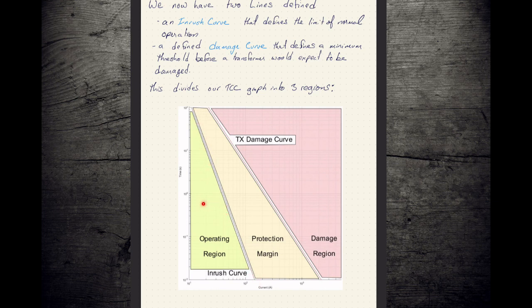And if you plot the points from the inrush curve on a log-log graph, it makes a mostly straight line. And we know that anything on this side, so anything less than our inrush curve, represents our normal operating region, right? Everything's hunky-dory as long as you're not above the inrush line. The inrush line is what we define as the upper bounds of normal operation. If you're under inrush, everything's good. If you're over inrush, things are bad. Operate your fuse.